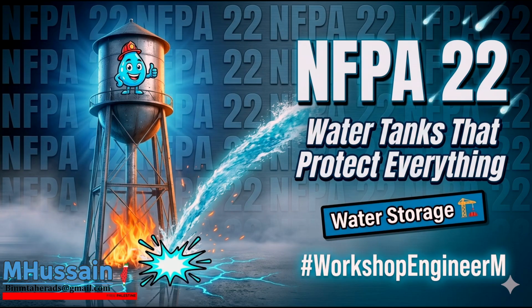And they must hold that pressure without dropping more than 0.5 psi over a full 24-hour period. That is an extremely tight tolerance. Yeah, practically zero allowable leakage. Because a slow pneumatic leak over 6 months means the system is entirely dead when a fire breaks out. But engineers need to be really aware of the thermodynamics during that 24-hour test.